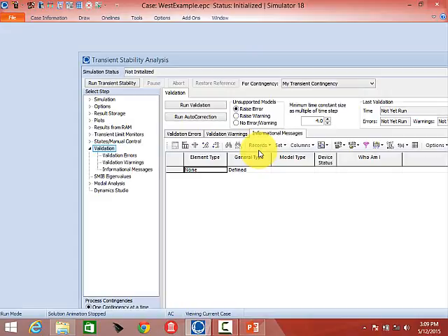coming into the case. We do have an option here, unsupported models. If you run a case with a model that PowerWorld doesn't support, we give options for what to do about it. This is less and less and less of an issue because we support just about everything now. But if you ran one and the model wasn't supported, we would want to let you know about that because your results aren't going to be what you expect. So we, by default, have it raise an error which just says that model's not supported.